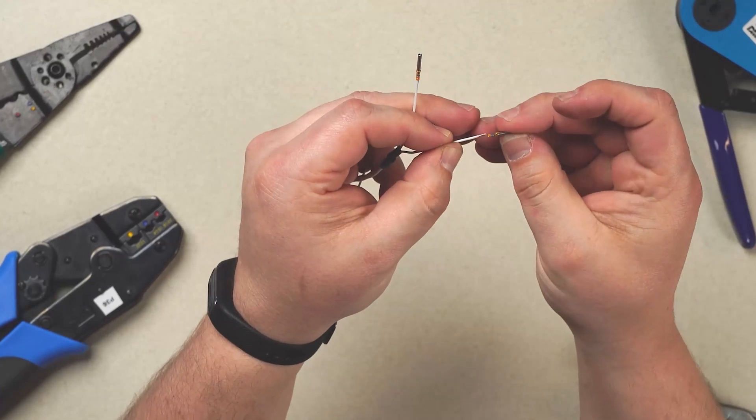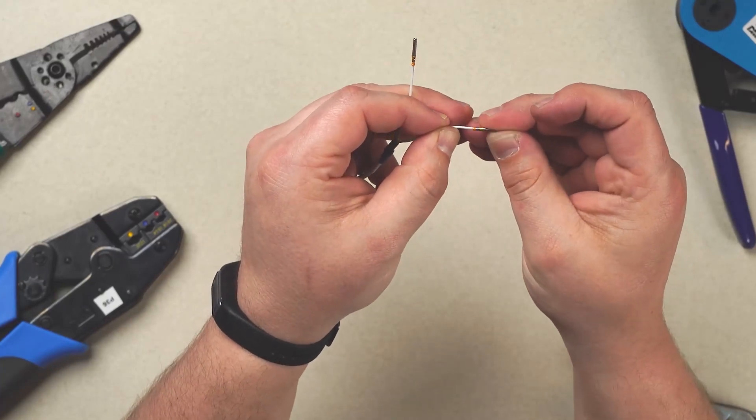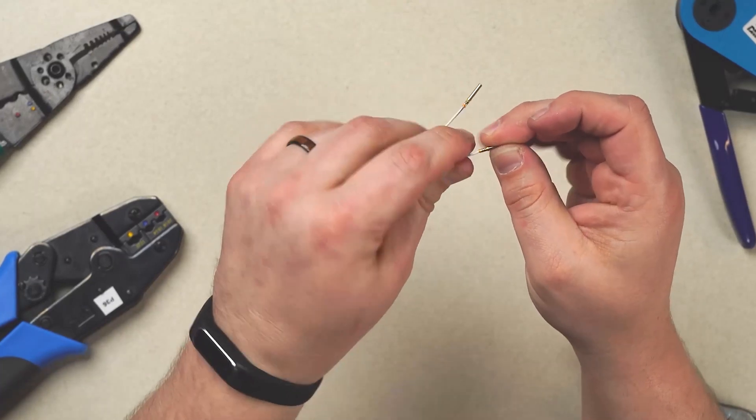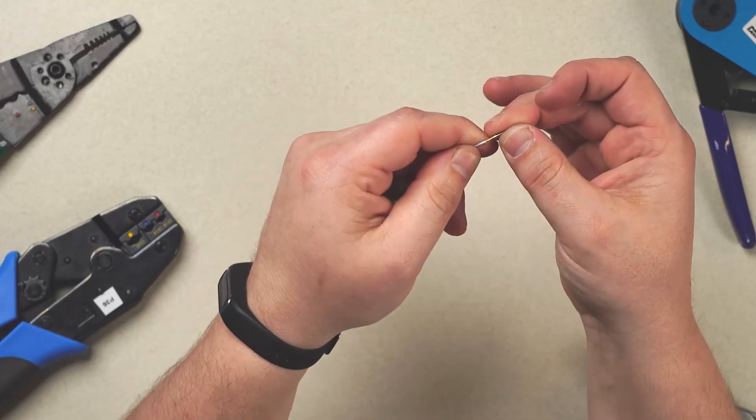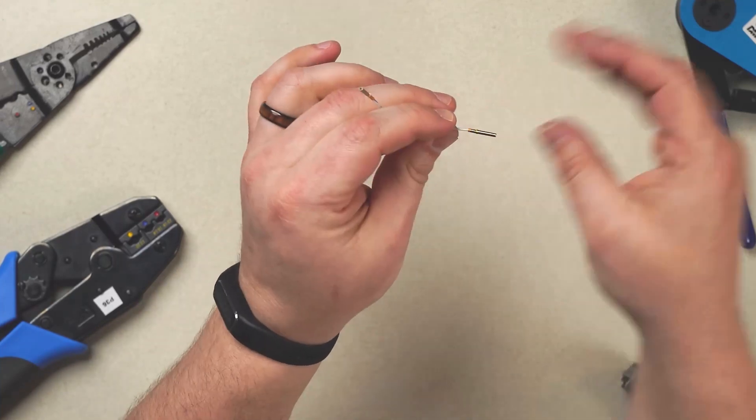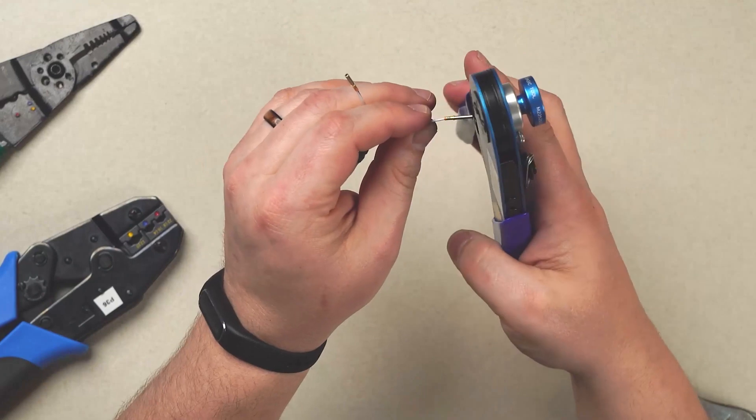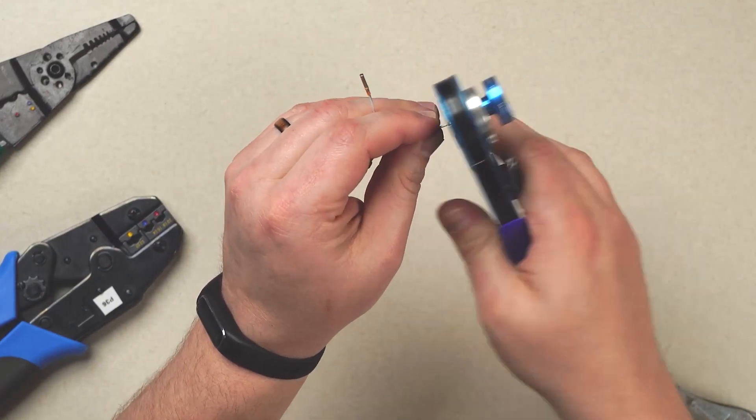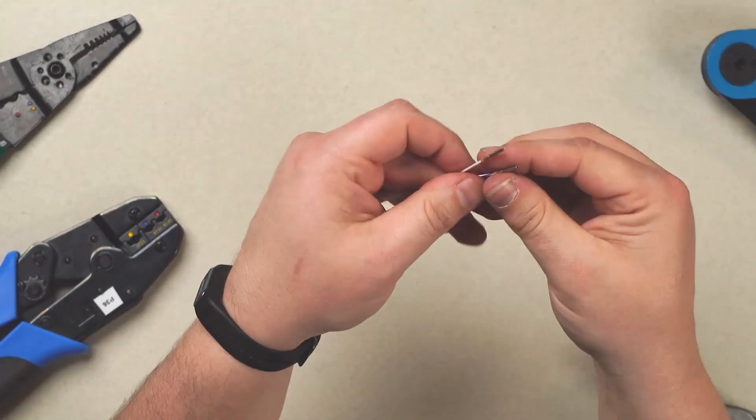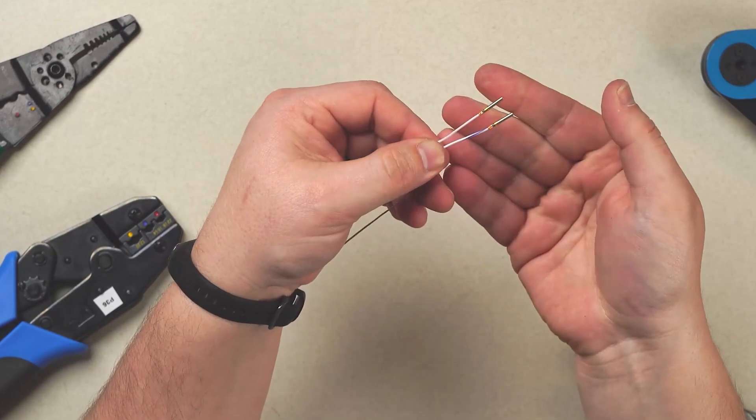Same thing on our second wire here. We're going to use the window. We see the wire in the window. We see that our insulation is not inside of the pin itself. So we're bottomed out properly. Crimper set properly. Well executed crimp every single time.